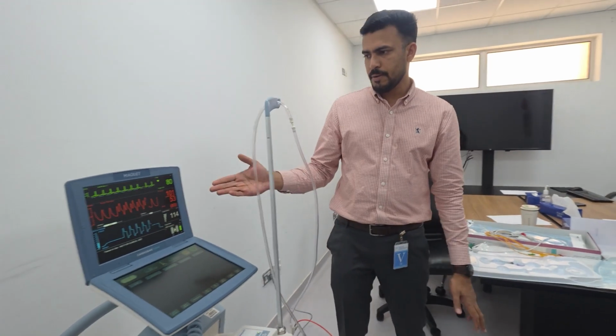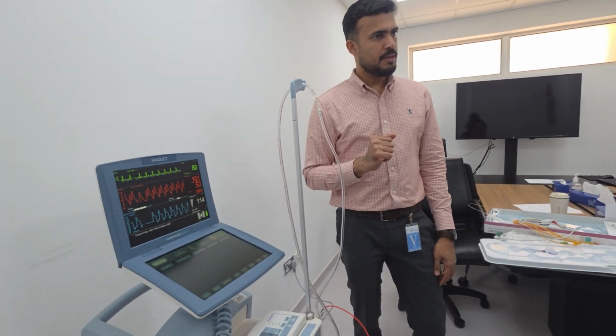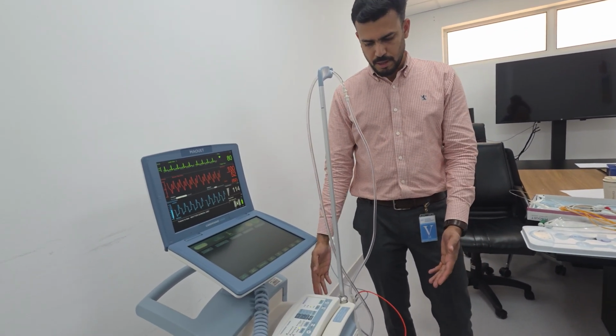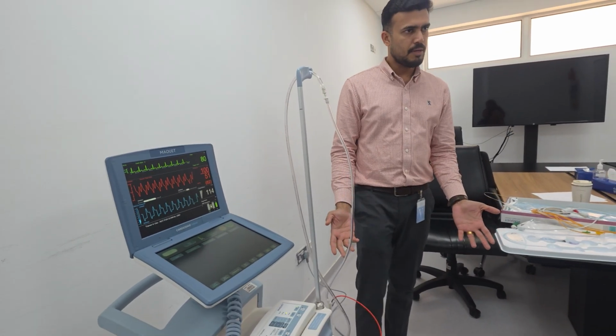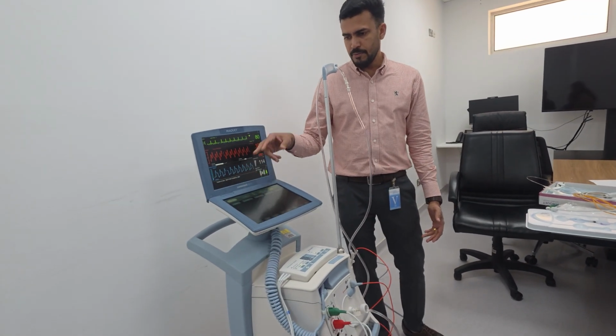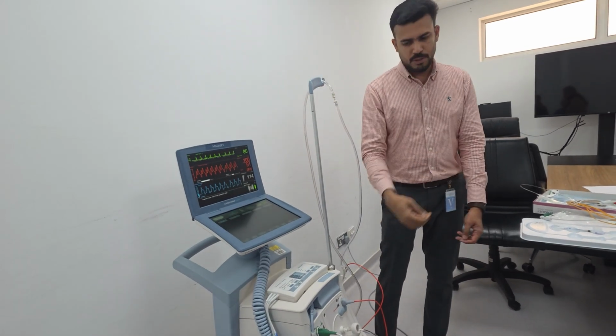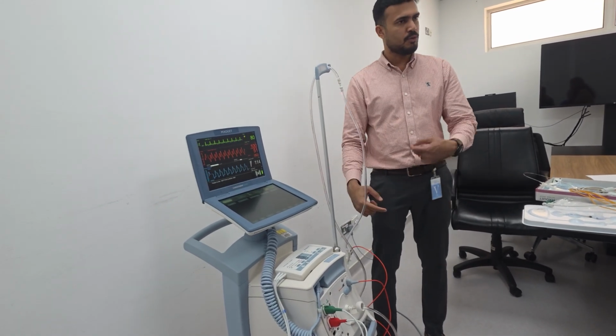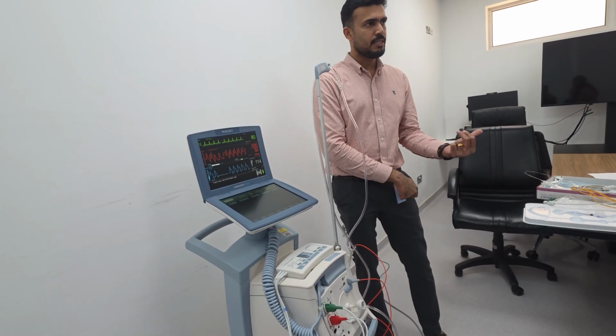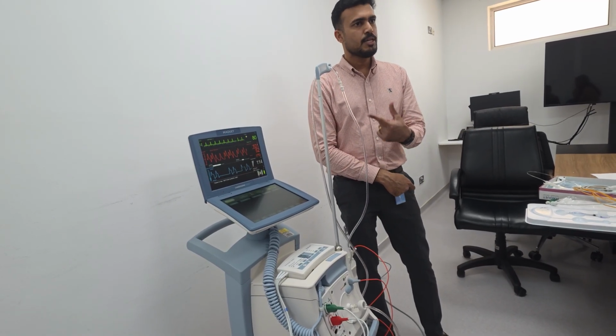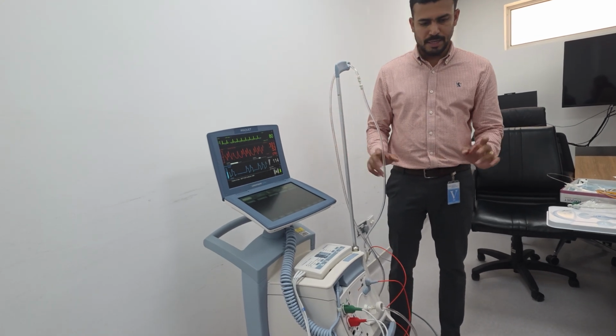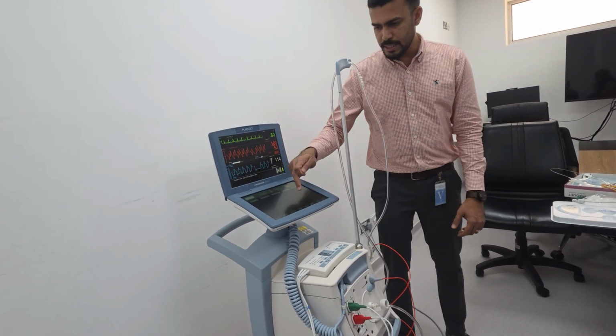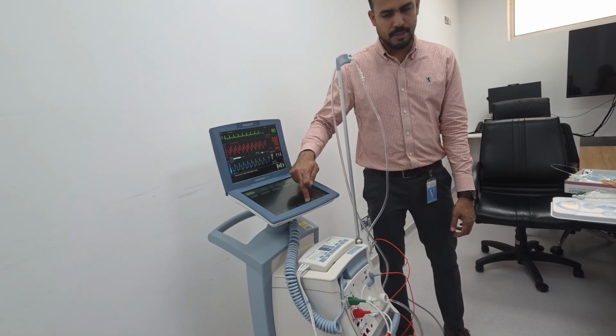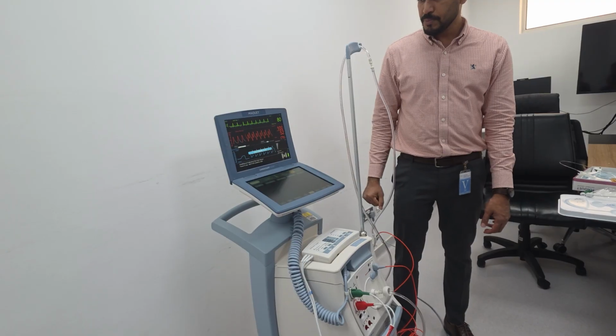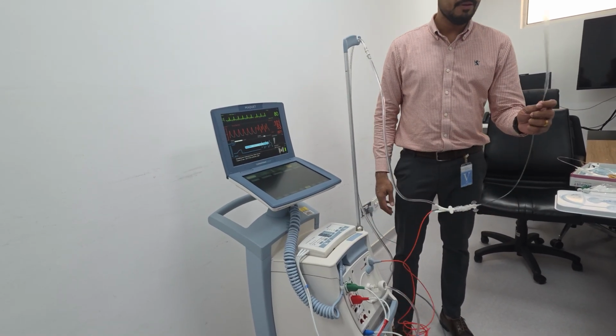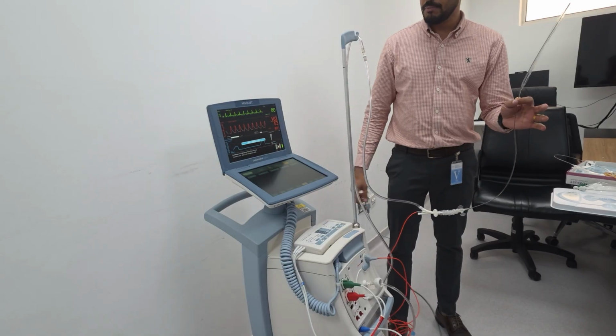But it's pumping. Suppose you are getting a low helium alarm. You know the balloon is pumping on a patient. We have to remove the helium. But as I mentioned, it's pumping. We don't know when the next autofill will be. So when you are removing the helium, maybe the machine initiated an autofill and it's looking for helium, but you have removed the cylinder. So it could be an autofill failure. So what to do when you have a low helium? Don't panic. Arrange your helium cylinder and just go and start a manual autofill. Okay, just do an autofill. It will refill with the new helium and give an indication that autofilling is complete.